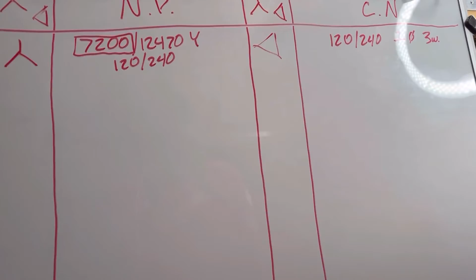So what's the rule? Remember, delta divides. So 120/240 single phase 3-wire, that's going to be a delta, isn't it? 120 divides evenly into 240, so it's going to be a delta. Now the next thing we need to ask is, can I fulfill my customer needs with this transformer? If the answer is yes, go ahead and write it in. We've got a delta. So the next one, we've got 4800 delta. So my circuit's a 4800 delta, phase to phase to phase, 4800 volts.